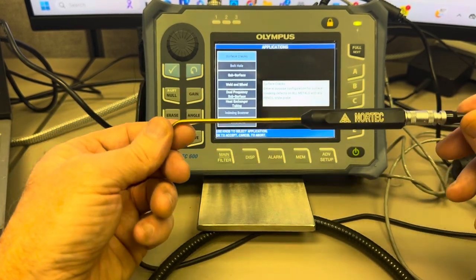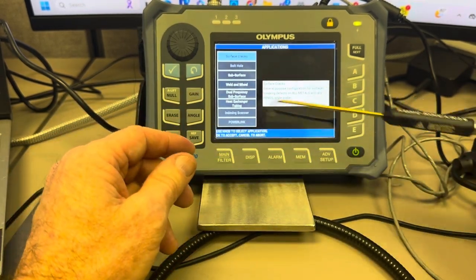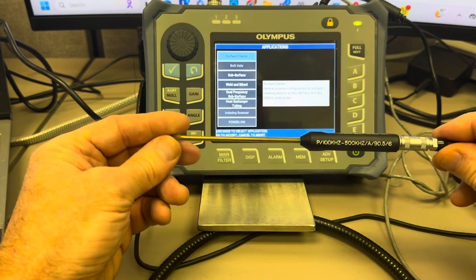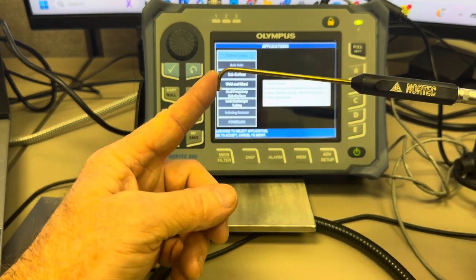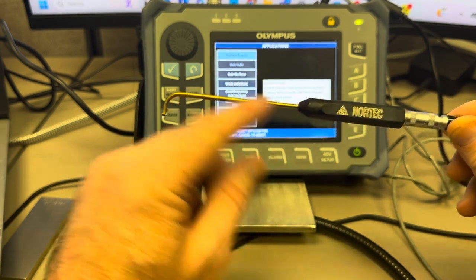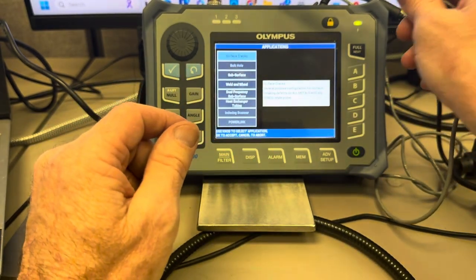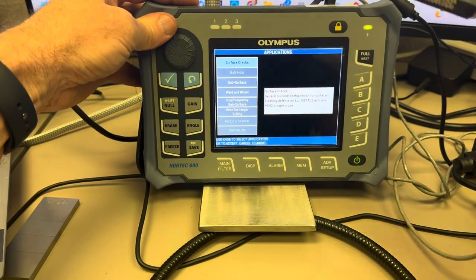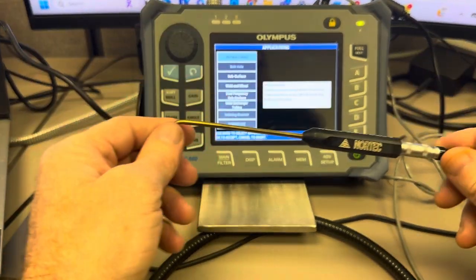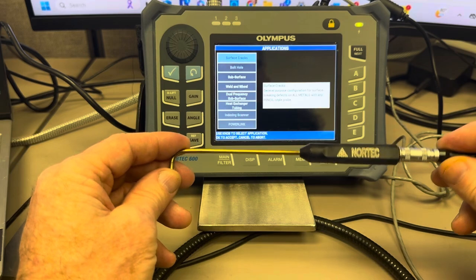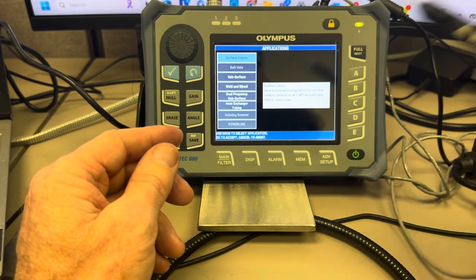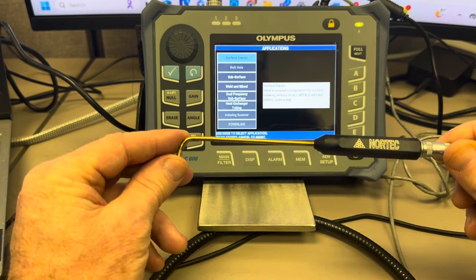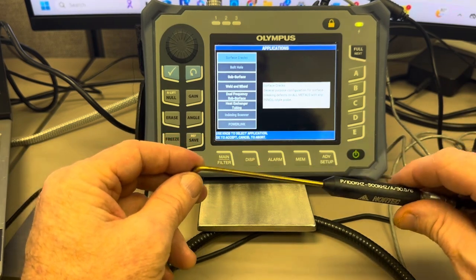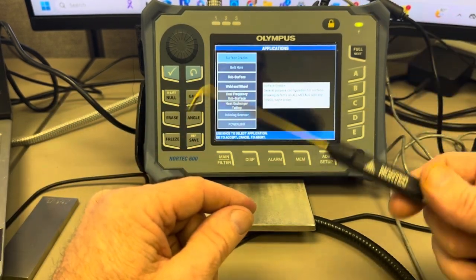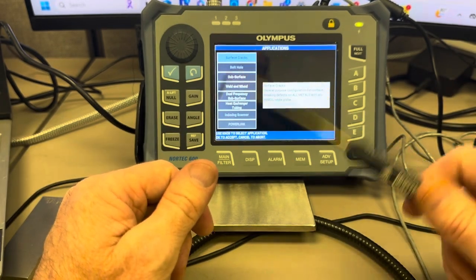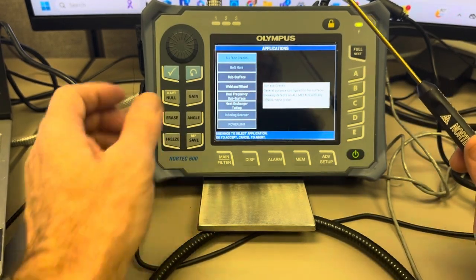Now, one of the setups in here is you can turn on power link. What power link is, if you have a newer probe, a lot of times there's a smart chip in it. So when you plug your 16-pin LEMO cable that's on the top here, you can see it on screen. But when you hook up a probe with a smart chip in it, the instrument will configure itself to have optimum settings for that particular type of probe. But this is an older probe, doesn't have a smart chip in it, so I can't use the power link feature. But I don't care because I know how to set this instrument up, and it doesn't take that much time.